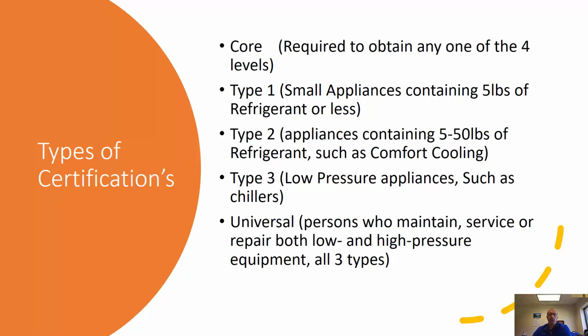Types of certifications: CORE, which is required to obtain any of the four following levels. Type 1, small appliances containing 5 pounds of refrigerant or less. Type 2, appliances containing 5 to 50 pounds of refrigerant, such as comfort cooling. Type 3, low pressure appliances, such as chillers. Passing all three types, you can obtain the universal license, for a person who maintains, services, or repairs both low pressure and high pressure equipment.